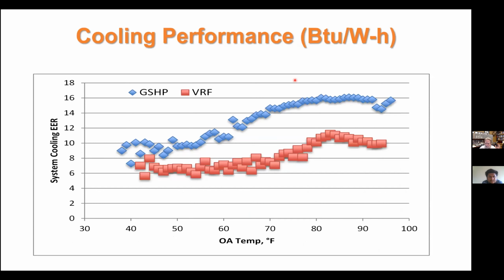and look at the performance of both systems for cooling versus the outdoor air temperature, you see something that I found very interesting when we started studying this. That is, generally, as it gets warmer outside, the system performance gets better. And I teach thermodynamics, and we generally tell students that if the source temperature gets higher, that we're trying to reject heat to, for the same inside conditions, the COP or EER should go down. But in fact it goes up and then flattens out when it's fairly warm. The VRF system, you see it goes up and it comes back down just a little bit.